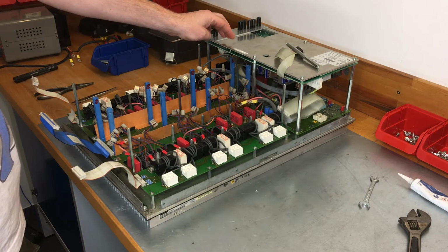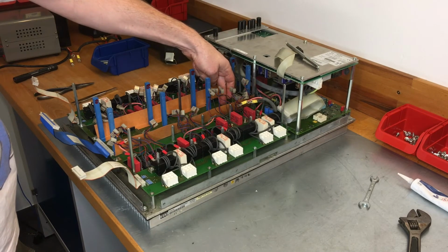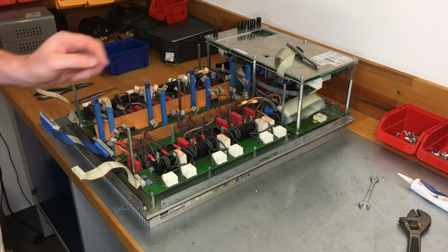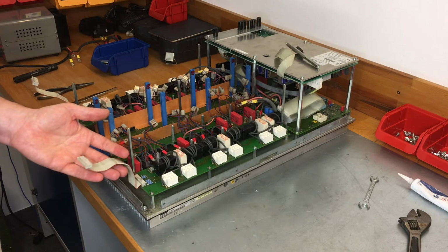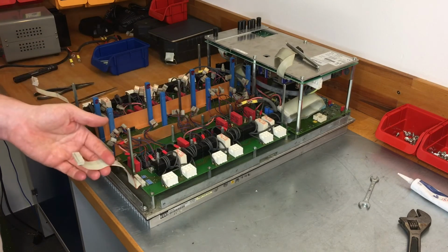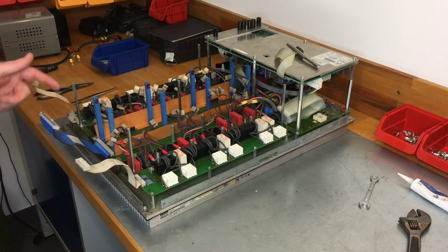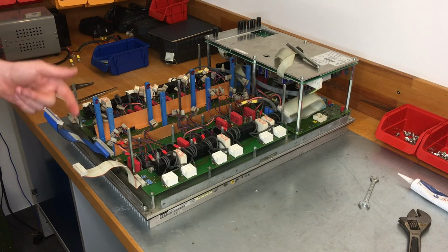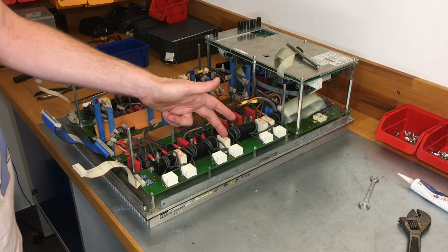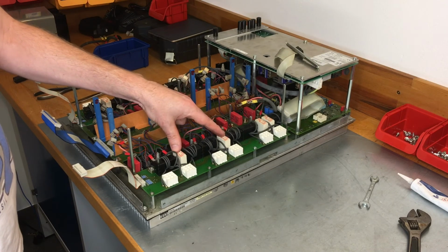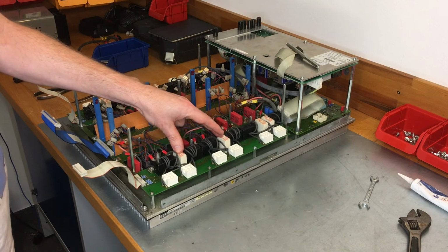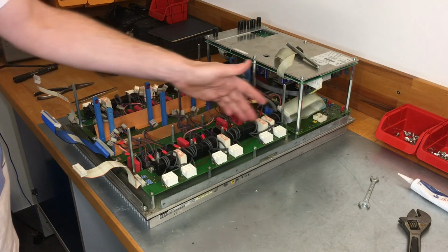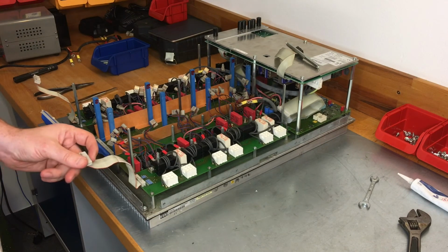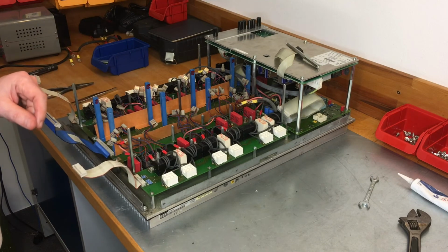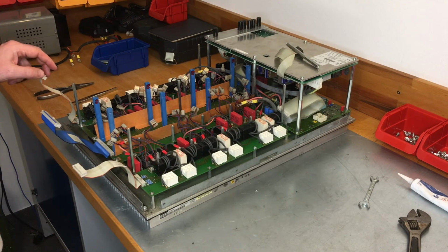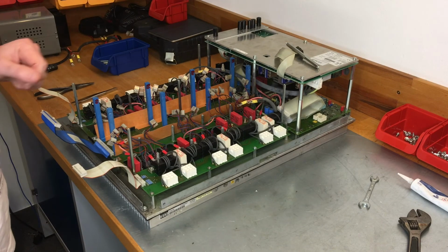For example, here comes the low voltage power supply to the mainboard and goes to the individual driver cards. Via the connector here, the logic board reads the measured current values directly, so the current values go directly up to the logic board. Here the individual PWM signals go from the logic board to the driver cards. The relays are normally closed, which means they have to be activated before the motor can be controlled. Otherwise, there would be a short circuit immediately. The relays are connected in parallel and are supplied with 24 volts via 2 pins here, so that they open symmetrically here on the other side in the same way. I think that's it for the main board.